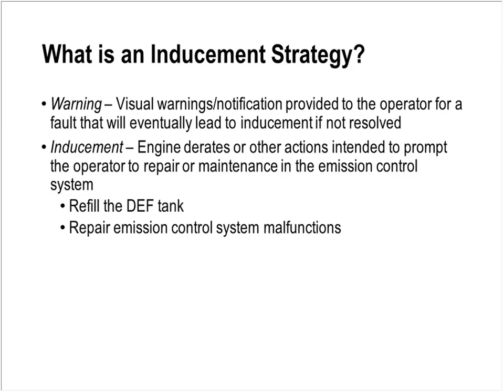For a generator, it will not be a derate. It will be a shutdown. And there's roughly a 4-hour period as the engine notifies the operator and then counts down towards a shutdown. There are a number of things that can cause this inducement strategy to initiate, but basically it's around the diesel exhaust fluid level or quality or a malfunction of the selective catalytic system and its sensors. That's the NOx reduction system.